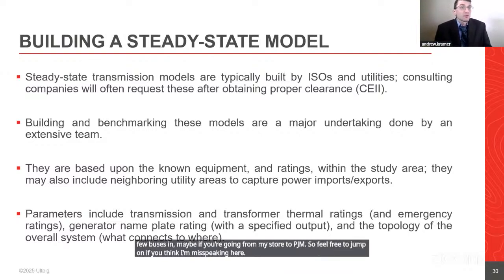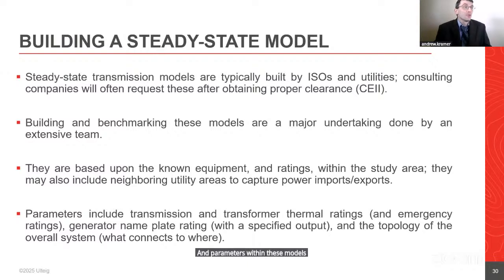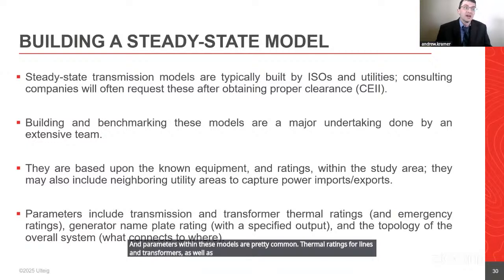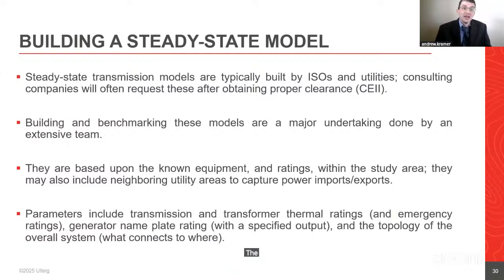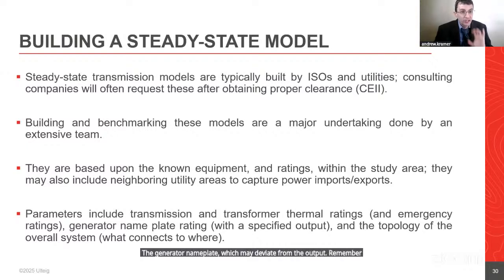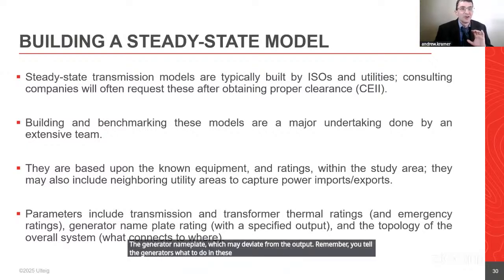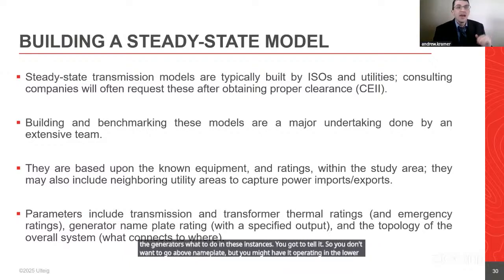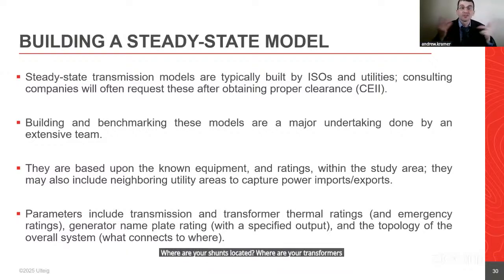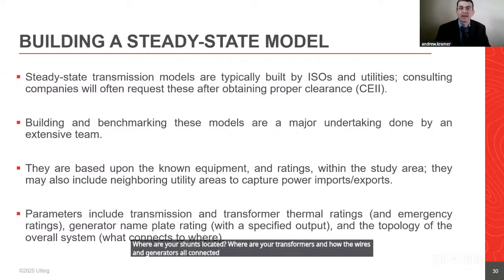Parameters within these models are pretty common: thermal ratings for lines and transformers, as well as emergency ratings, and the generator nameplate, which may deviate from actual output. Remember, you tell the generators what to do in these instances. You don't want to go above nameplate, but it might be operating at a lower state at some point. Then you also have the topology of the system: where your shunts are located, where your transformers are, and how the wires and generators are all connected to each other.